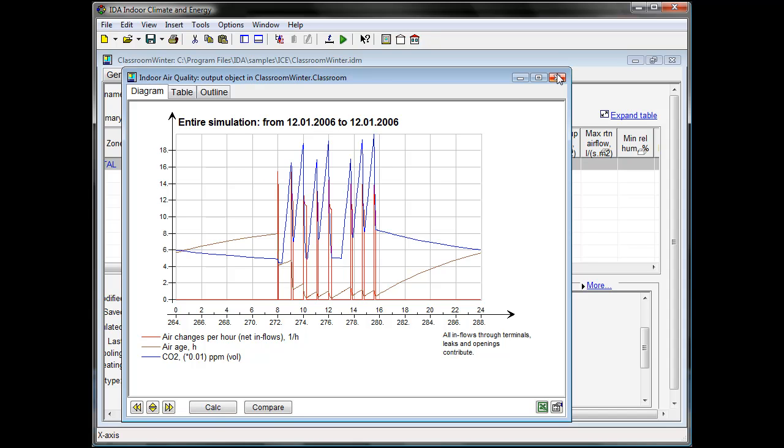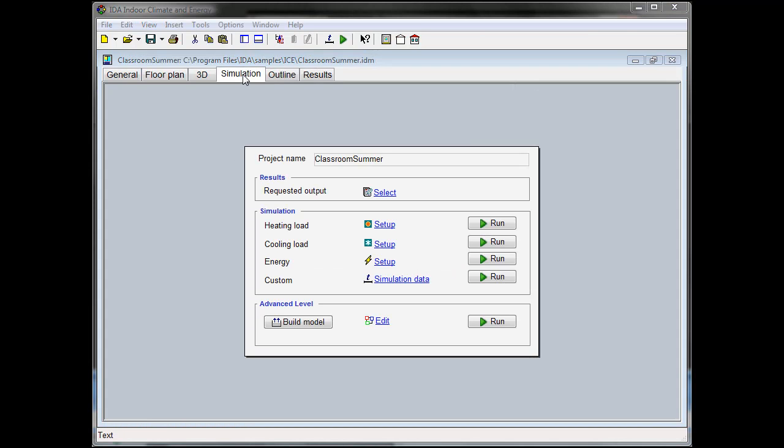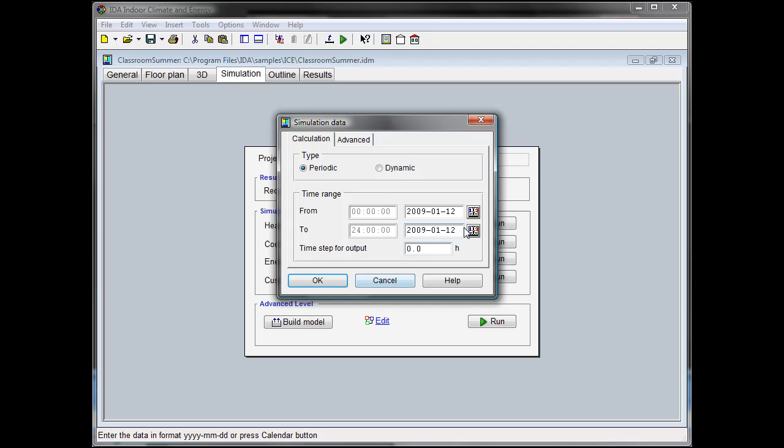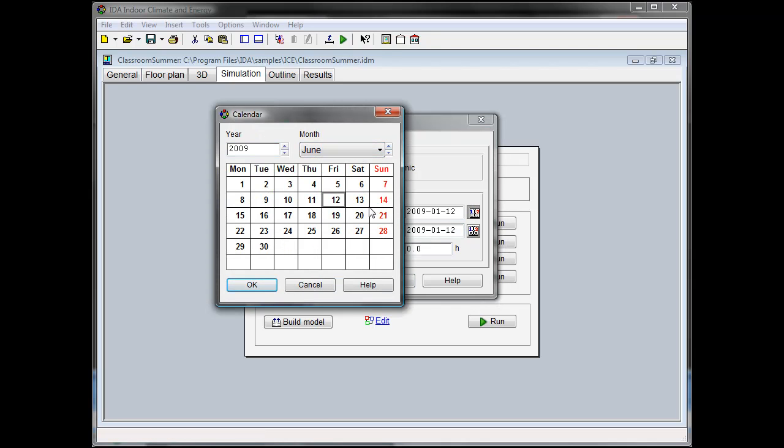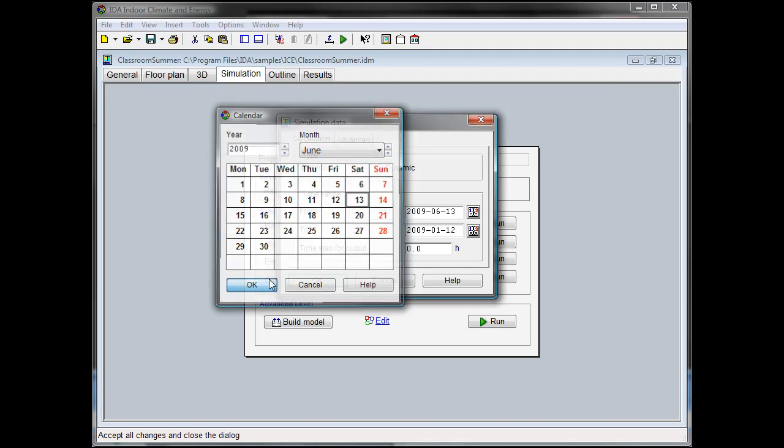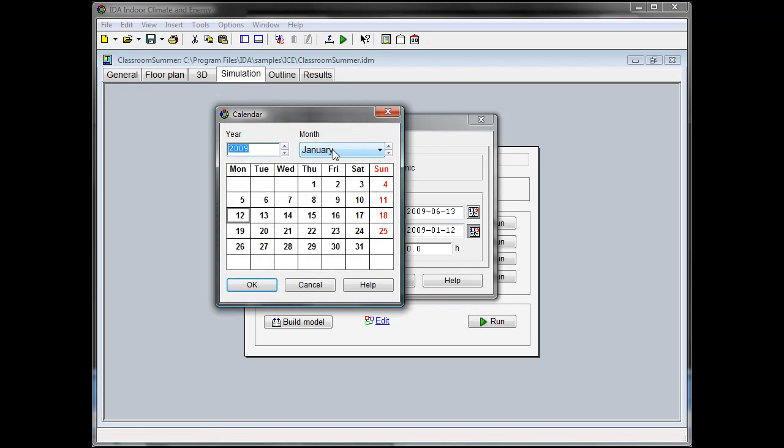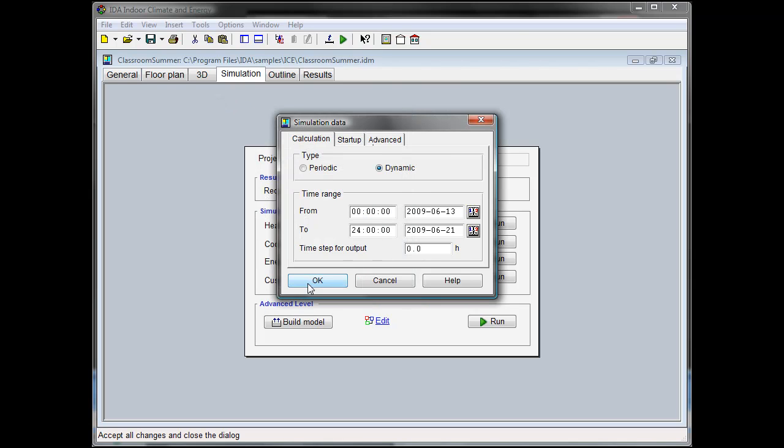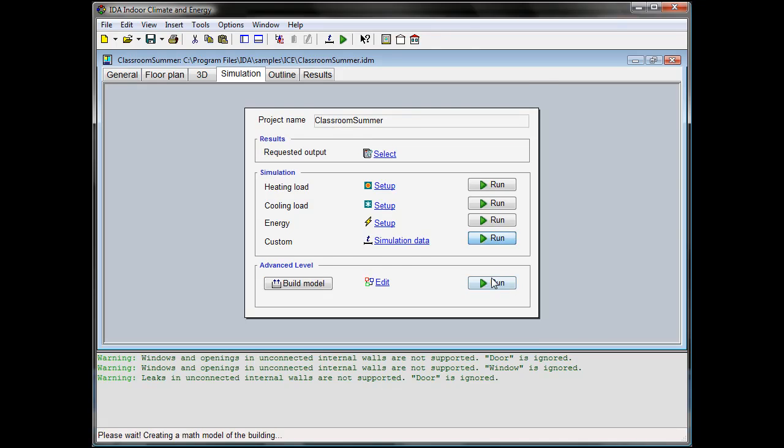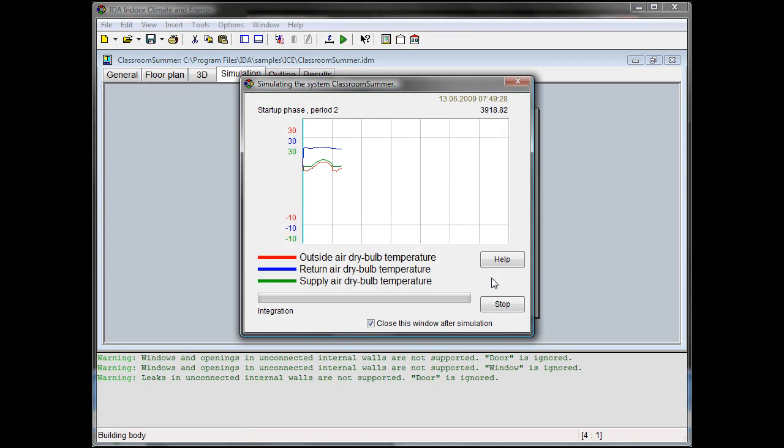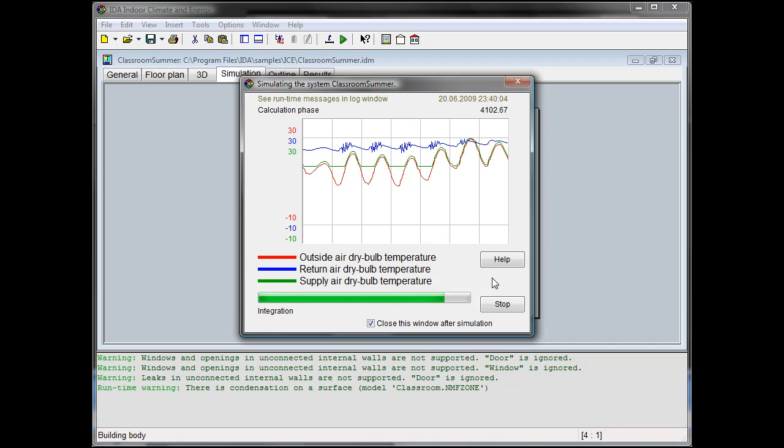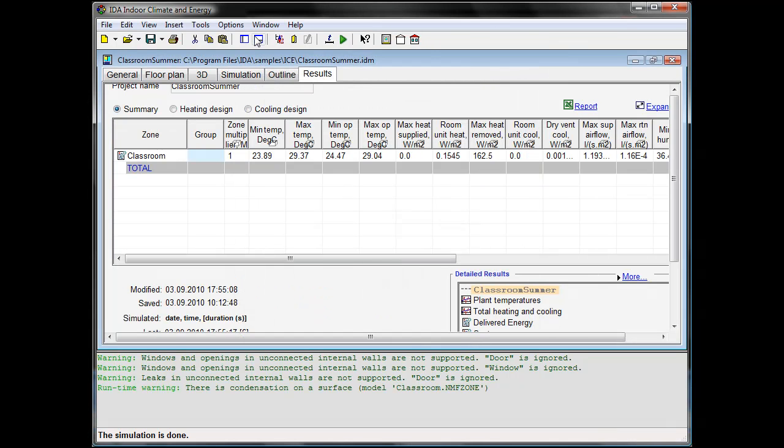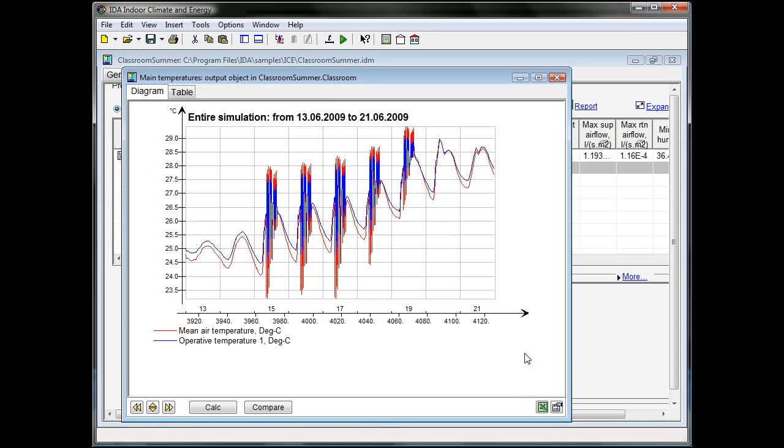So far the winter situation, but let's now have a look at the summer situation and change simulation period to a week in June. We start at 13 and go to 21. First let's do the simulation. And looking at the results we can see that the room temperatures are rising from day to day during the whole week, reaching 29 at the end.